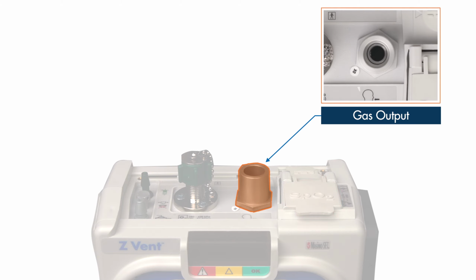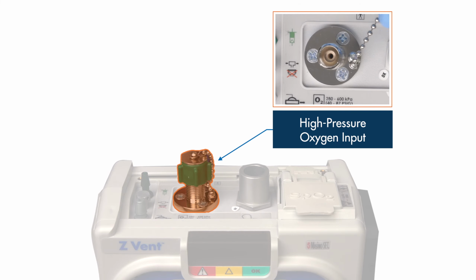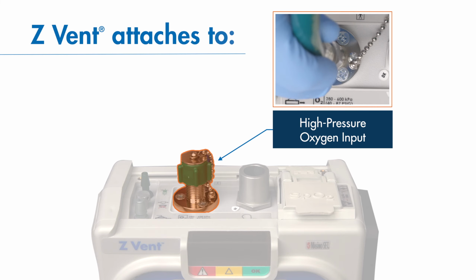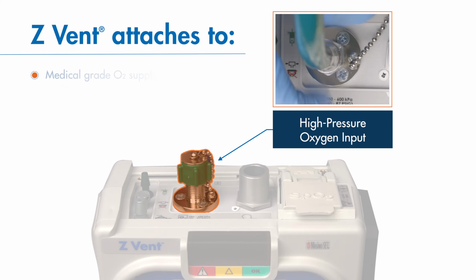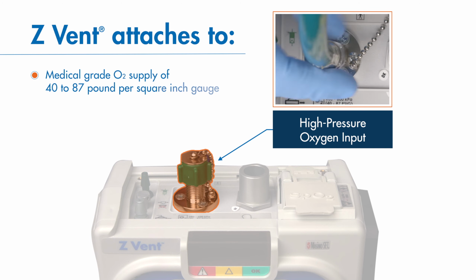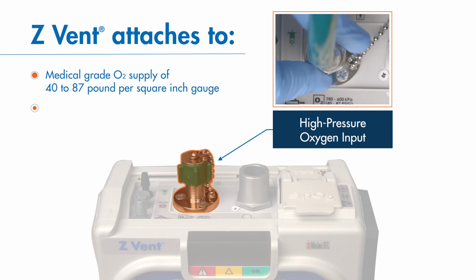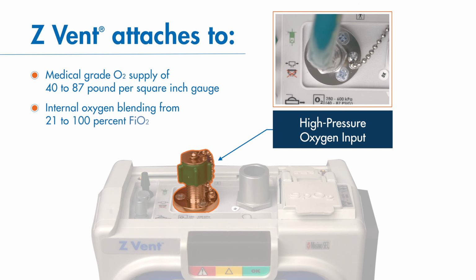In the middle, the silver cylindrical port is the primary gas output for the patient inspiratory circuit line. To the left, the threaded port with the green screw cap is the high-pressure oxygen input. The Z Vent can attach to a regulated medical-grade O2 supply of 40 to 87 pounds per square inch gauge. This connection allows for internal oxygen blending from 21 to 100% FiO2.